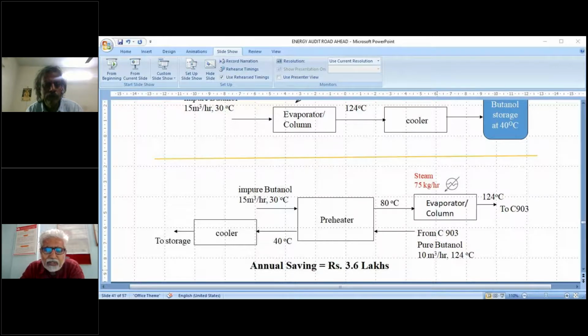Sir, in some industries, the steam condensate is available at around 40 to 50 degrees Celsius maximum after going through all the processes, and there is no need for the heat at that particular temperature. So how can that heat content be conserved and utilized for some application? For example, in the paper and pulp industry, we observed that after completion of the process, that condensate is available, and they don't need it anywhere, not even as makeup water or as condensate to the boiler.